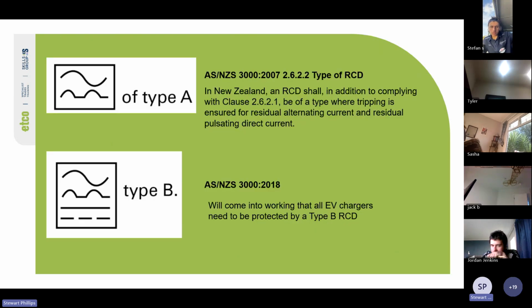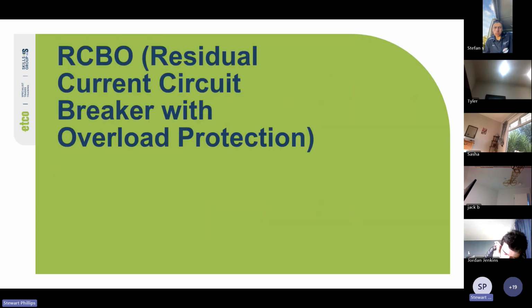Cool. So there's two types. You've got type A. In New Zealand, according to 2007, 2.6.2.2 type of RCD: in New Zealand, an RCD shall, in addition to complying with clause 2.6.2.1, be of a type where tripping is ensured for residual alternating current and residual pulsating direct current. And then you've got type B. So we'll come into working that all EV chargers need to be protected by a type B RCD. So it's AC, ripple or pulsating DC, and ripple-free DC as well. It needs to be able to protect against DC because EV chargers spit out DC to the cars. Cool.